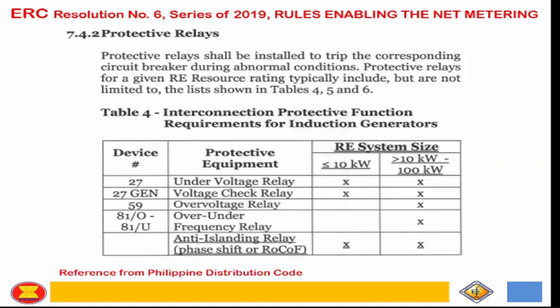Kaya during our introduction, diniscuss natin what are the basic types of generators, no? Kasi na-mention dito yung induction, yung synchronous at saka yung asynchronous. And these are the protection requirement, no? Under net metering rule, no? So above 10 kilowatt, less than 10 kilowatt under over voltage, no? And then the ROCOF, no? So yung sabi ko na although your practice, no, there's some practice na communication or transfer tripping yung DG, but maybe it's not practical na magiging may invest ka with the communication transfer tripping for that small generating plant, no, micro. But there's what we call the rate of change of frequency, the ROCOF.